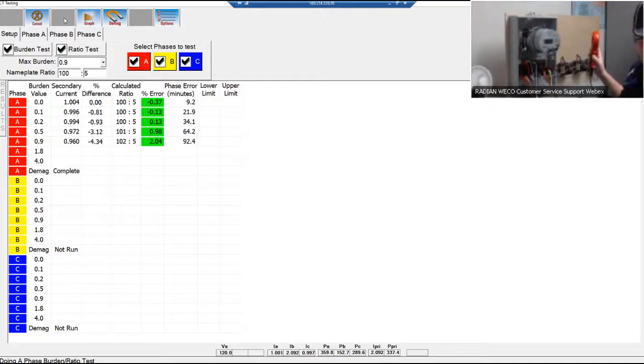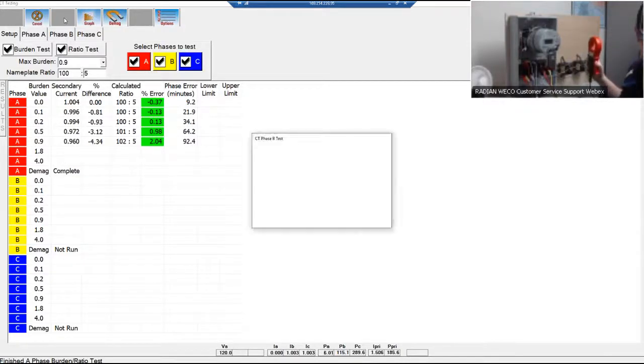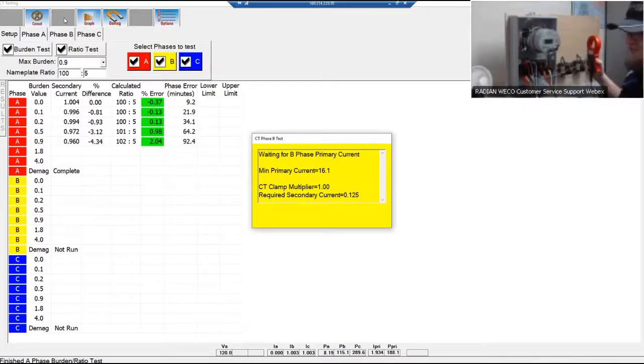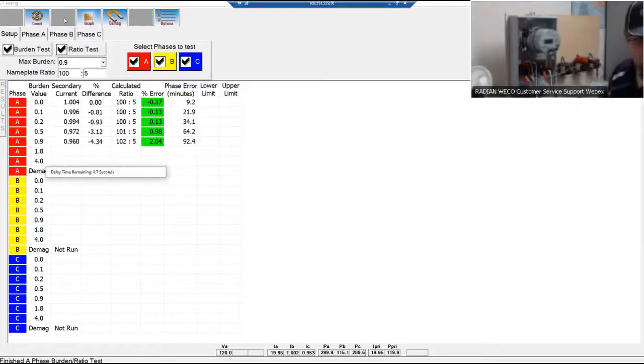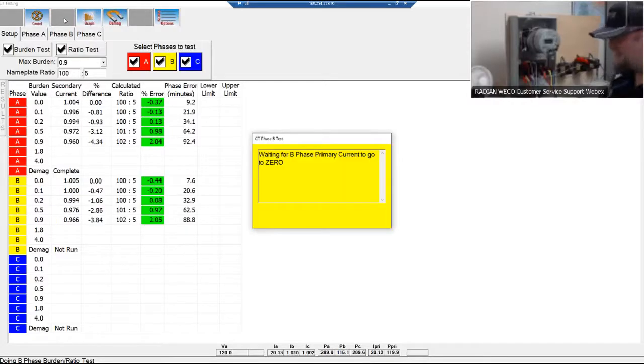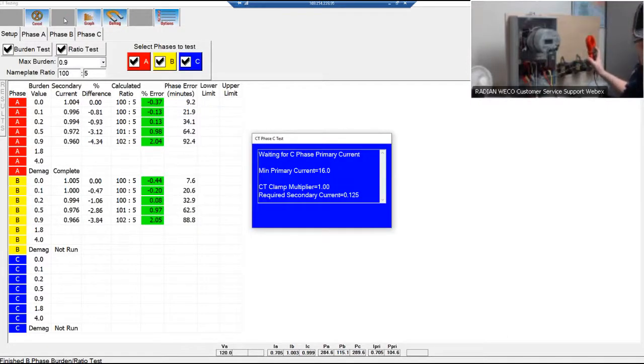And here in a second, it's going to pop up waiting for B phase primary current. So now it's waiting for the same thing, except on B phase. So now we're going to move my probe over to B phase primary, and repeat the test. Now for B phase. Same thing. Now it's waiting for my B phase current to go to 0. It's waiting for me to pull this off. And now it's waiting for C phase.